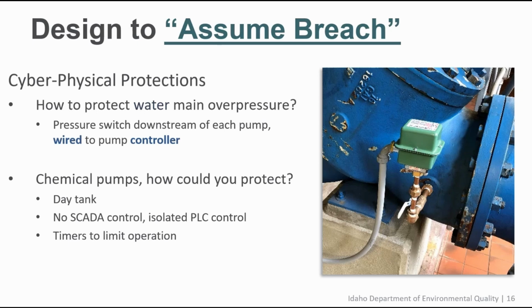The key is that the pressure switch needs to be wired directly into the motor controller, not through the PLC, because that would take away the whole purpose of doing this. Having that pressure switch wired directly to the controller means it will operate the pump or keep it from going into overpressure even without a PLC or SCADA system. Now, how would you protect chemical pumps?